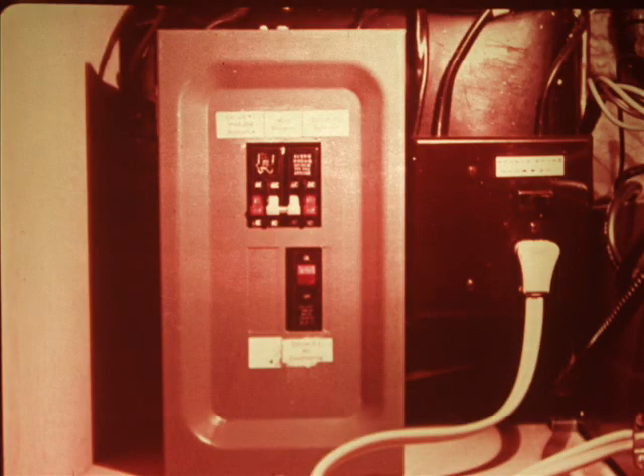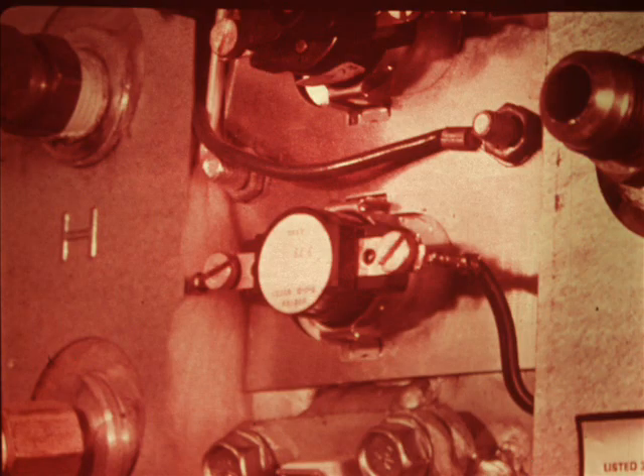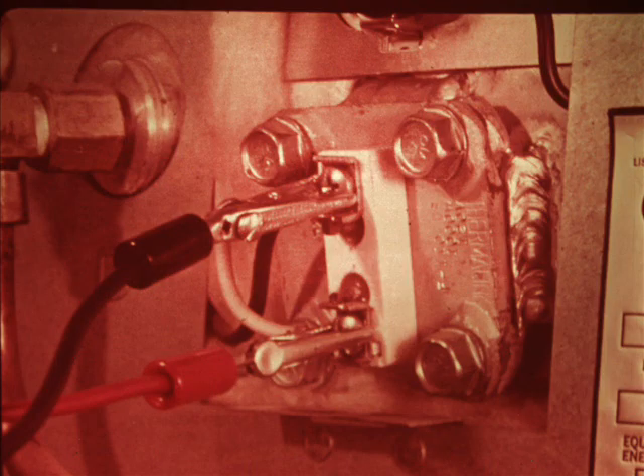Next, check the circuit breaker in the electrical compartment to make sure the circuit hasn't opened. Check the thermostat. Again, you must remove the access cover. Connect a probe to the electrical lead going to the heater. If 120 volts is not going to the heater, the thermostat is defective. To remove it and put in a new one, take off the nuts that hold the thermostat cover plate in place, disconnect the electrical leads, and pull out the thermostat.